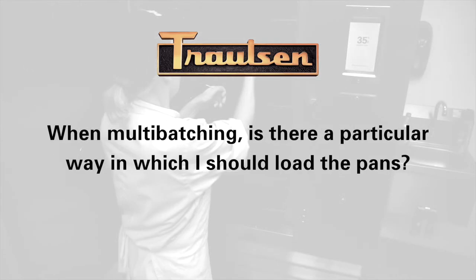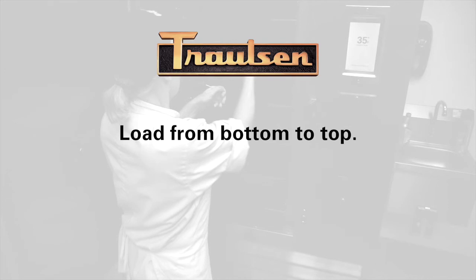When multi-batching, is there a particular way in which I should load the pans? When multi-batching, it is recommended that each batch be loaded from bottom to top. This is because heat rises, and loading pans in this way prevents heat from a newly loaded batch affecting the chill time of those located below it.